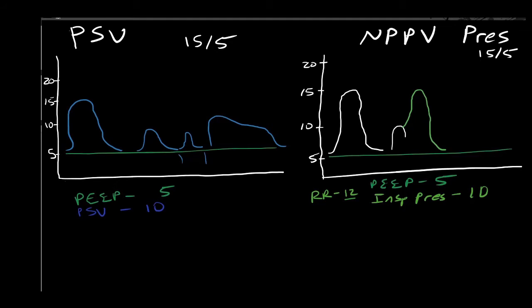This is very, very similar. In fact, there is no difference between the invasive mode pressure AC and NPPV pressure. NPPV pressure is basically BVM mode, and if your patient's not breathing fast enough on a non-invasive mode, what would you do in the field? Let's say you put them on CPAP in the field and they're not breathing fast enough. They're breathing too slow, they're too fatigued. What would you do? You would grab the BVM and use the BVM with PEEP to provide that minimum respiratory rate that you desire them to have. And so NPPV pressure lets you dial in a rate. It also lets you dial in an I time, which will always default to 1.